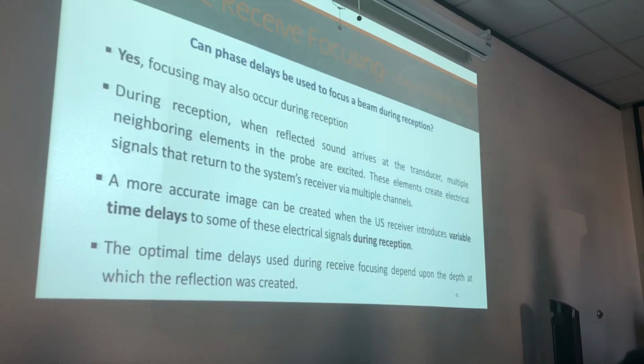Okay. So let's talk about the last thing, guys. Dynamic receive focusing. Can phase delays be used to focus a beam during reception? Of course it can. Yes, it can. Focusing may also occur during reception. During reception, when the reflected sound waves arrive at the transducer, multiple neighboring elements in the probe are excited. Okay? These elements create electrical signals that return to the system's receiver via multiple channels. Okay? Dynamic receive focusing works and creates a more accurate image. When the ultrasound system receives variable time delays, the electrical signals aren't being sent out at exactly the same time. So when they come back, these time delays are also applied during reception. Okay, that happens automatically. We don't control the dynamic receive focusing, or it's called dynamic focusing.